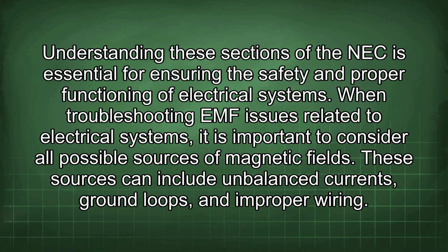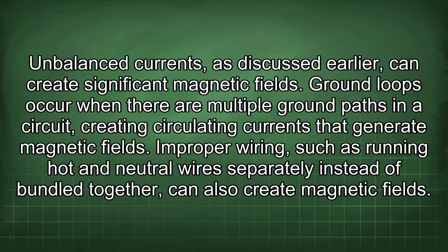When troubleshooting EMF issues related to electrical systems, it is important to consider all possible sources of magnetic fields. These sources can include unbalanced currents, ground loops, and improper wiring. Unbalanced currents, as discussed earlier, can create significant magnetic fields. Ground loops occur when there are multiple ground paths in a circuit, creating circulating currents that generate magnetic fields. Improper wiring, such as running hot and neutral wires separately instead of bundled together, can also create magnetic fields.